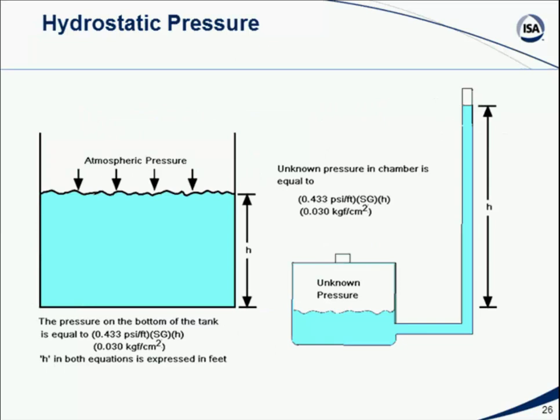One of the earliest types of pressure measurement devices was something called a manometer. A manometer is basically a tank of liquid with a vent on top into which we can push a pressure, so we can put a gas pressure or something else into the top of this tank. The tank is filled with liquid, which is then pushed out into a vertical column, again a sight glass. Based on the pressure pushing into this reservoir of fluid, we will push the fluid to a greater and greater height, h.